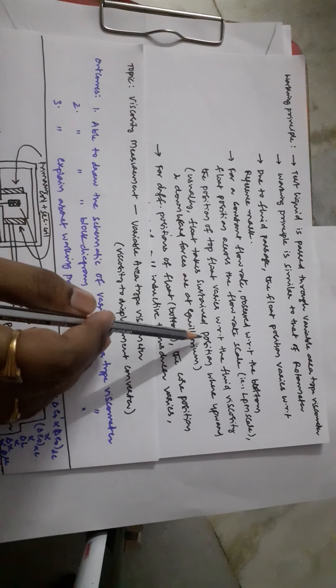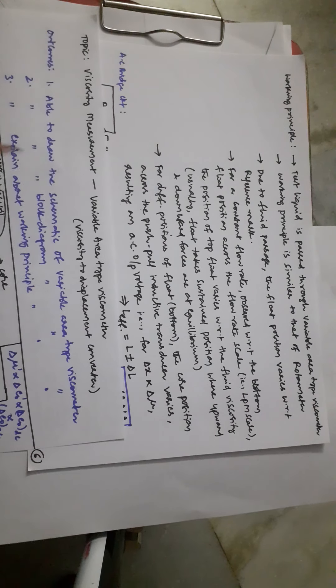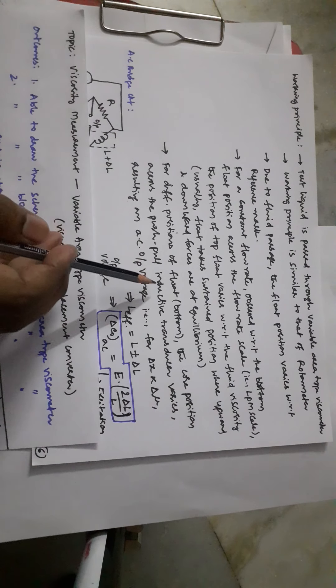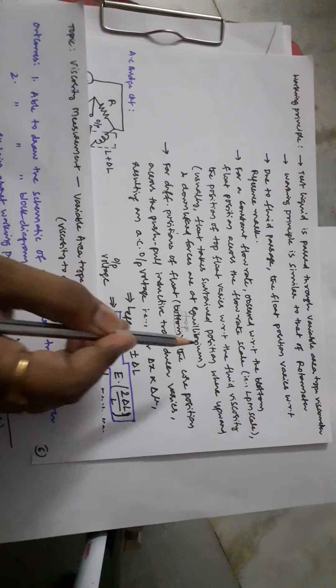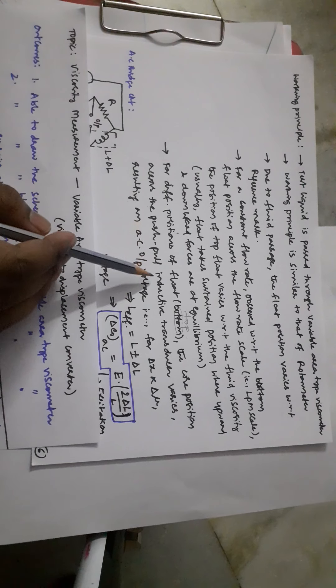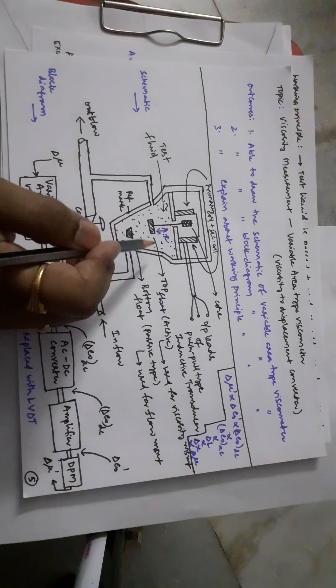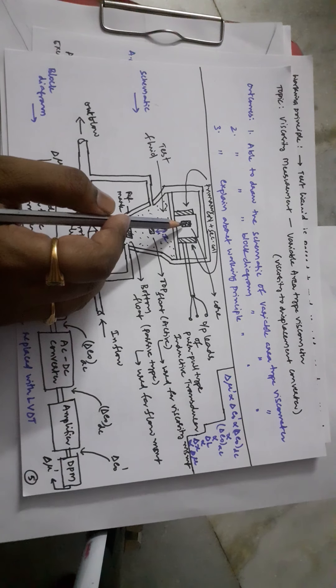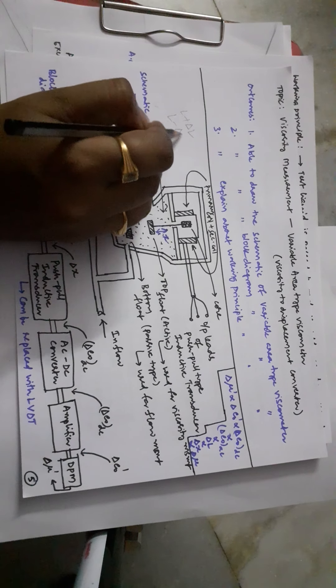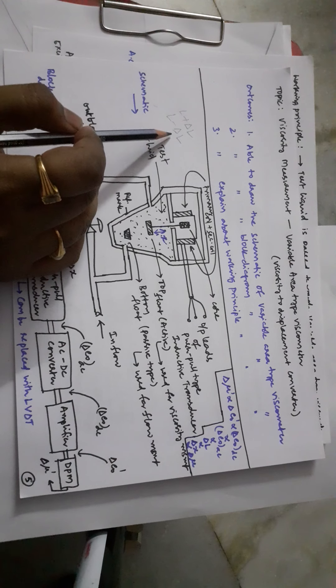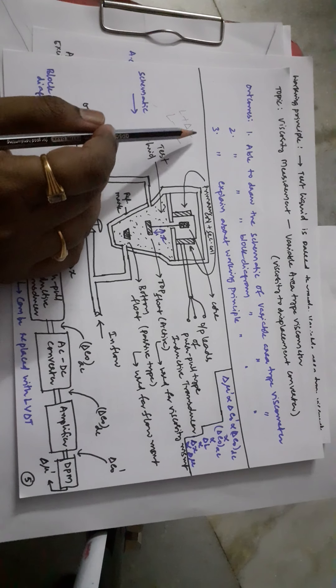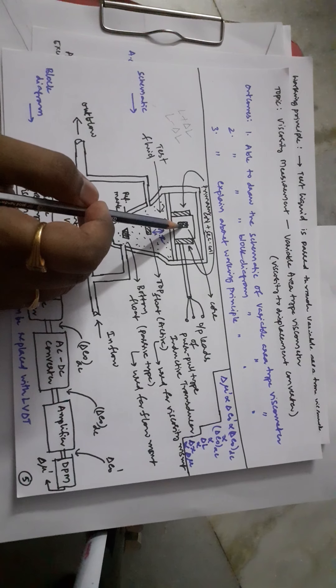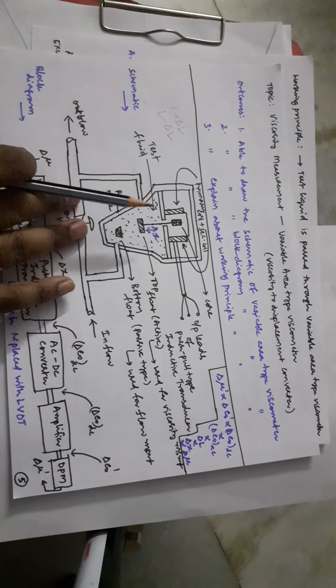The float takes a sustained position where upward and downward forces are at equilibrium. For different positions of the top float, the core position across the push-pull inductive transducer varies, resulting in an AC output voltage. As the float moves, the inductance changes: one coil's inductance becomes L + delta L and the other becomes L − delta L — one is pushed and one is pulled. This core position change causes one side's inductance to increase and the other to decrease.